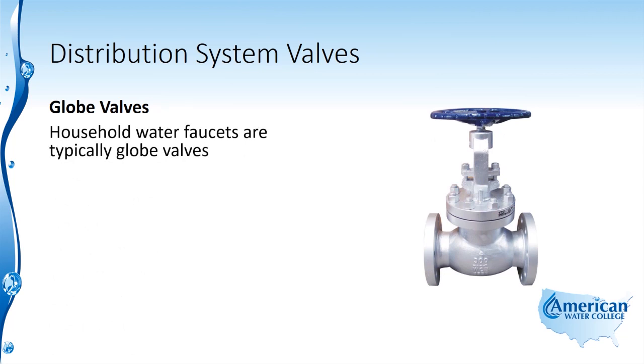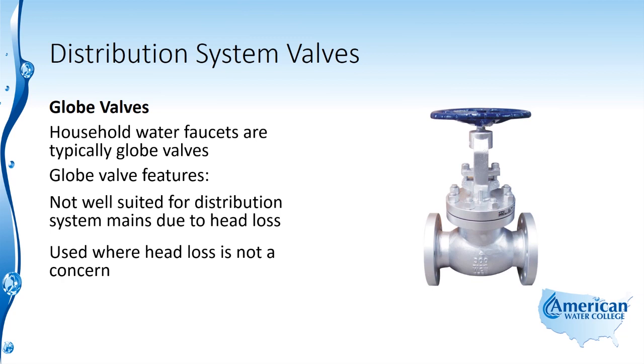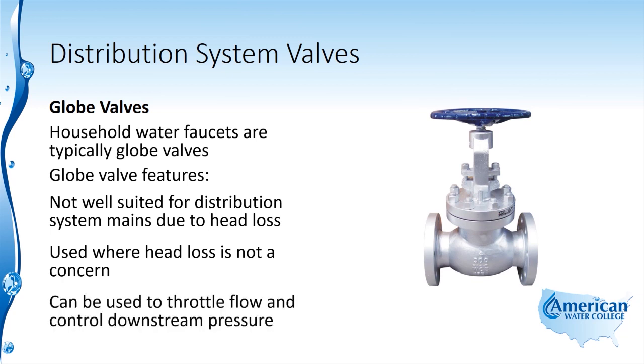Globe valves are a different type of valve, and household faucets are typically globe valves. Globe valves are not well suited for distribution system mains because of the high head loss within the globe valve. They are used where head loss is not a concern, but they can be used to throttle flow and control downstream pressure in high pressure, high flow situations.